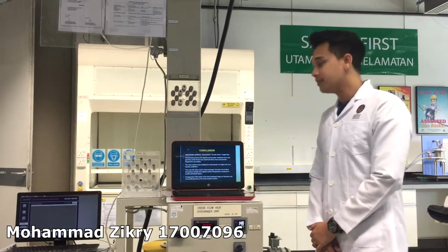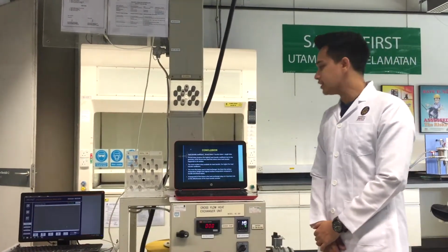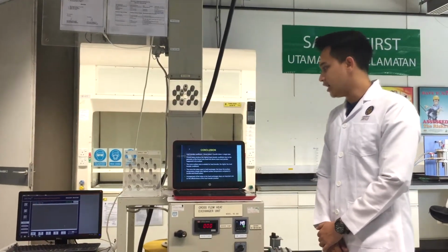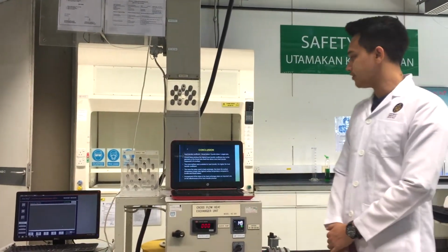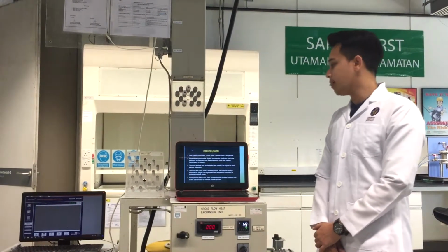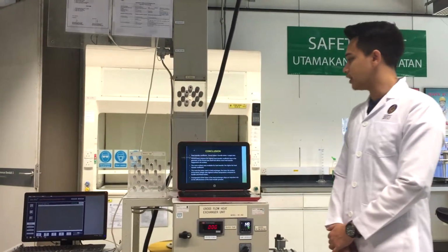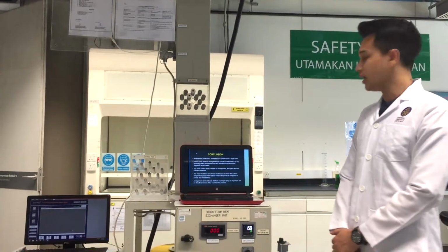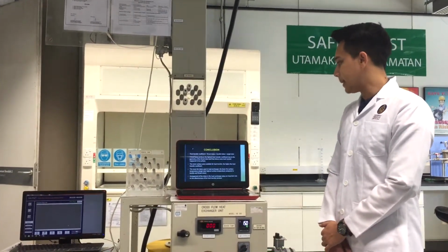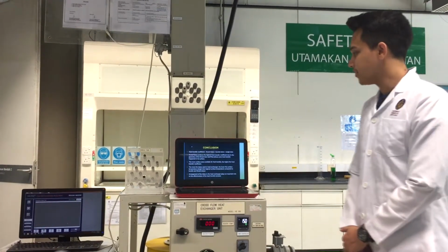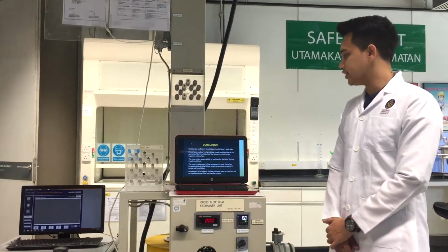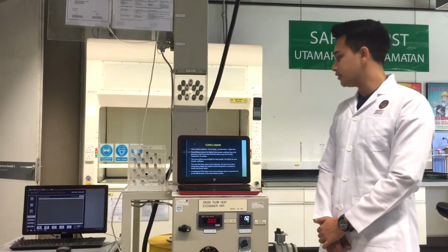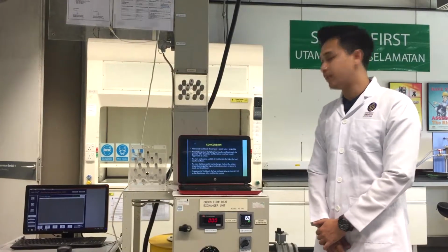As a conclusion, the heat transfer coefficient is the highest if you use the fin tubes, followed by the bundle tube and then the single tube. The fin tube produces the highest heat transfer coefficient due to the geometry of the tube itself, which allows more heat transfer to happen on its surface. The more surface available for heat transfer, the higher the heat transfer coefficient. Also, the more tubes used in the heat exchanger, the lower the surface temperature. This means that the single tube has the highest surface temperature compared to the others.